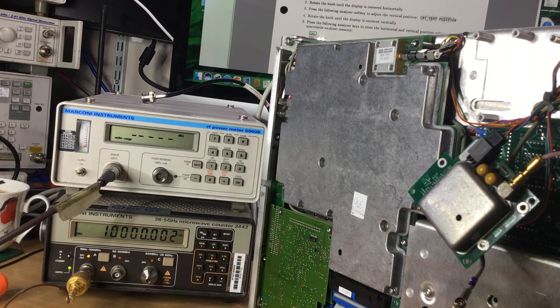And obviously in this case the 300 megahertz signal isn't, both the amplitude's failed as well as the frequency, and the fact that the calibrator output is wrong frequency and level wise, it's not down to this 10 megahertz oscillator obviously, because if we can't adjust it.